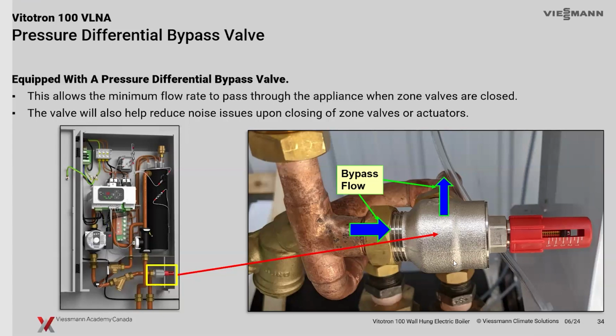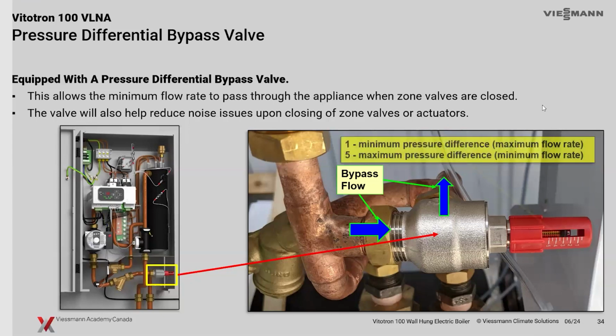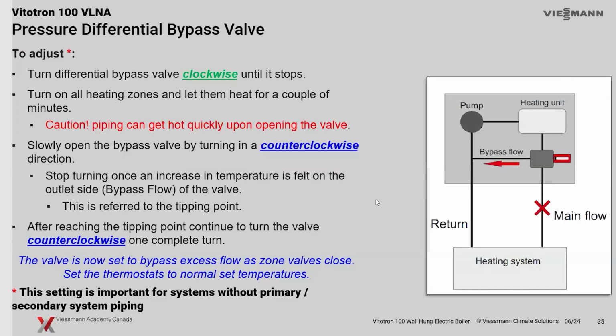It just kind of sits at the bottom portion with a little red cap on it at the bottom of the little electric boiler. And you've got your different pressure ranges here from 1 to 5. And we're just going to set this up. Essentially, we're going to make sure that all the zones are open and that you've got full flow.